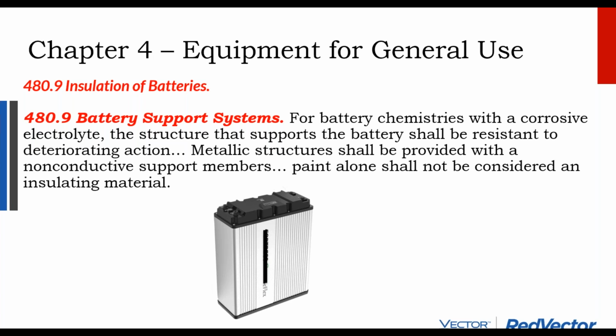For battery chemistries with a corrosive electrolyte, the structure that supports the battery shall be resistant to deteriorating action. Batteries are heavy. When you're building a battery room, you put them on a shelf or a rack, and more likely than not, that shelf or battery rack is built out of metal. So it's like, well, hold on, I'm putting something very conductive on a metal support structure.